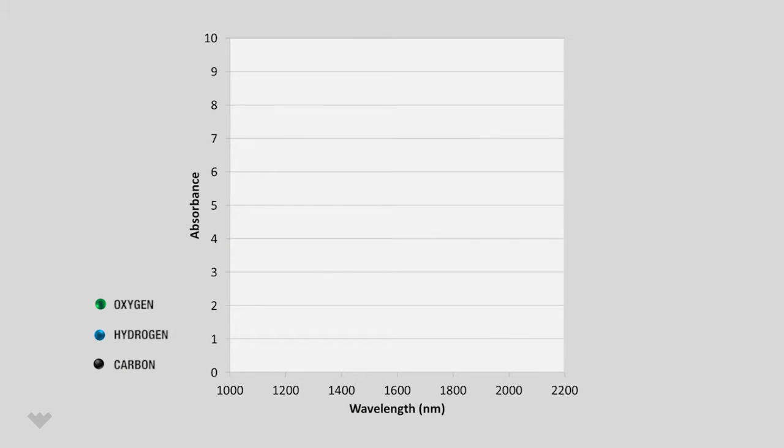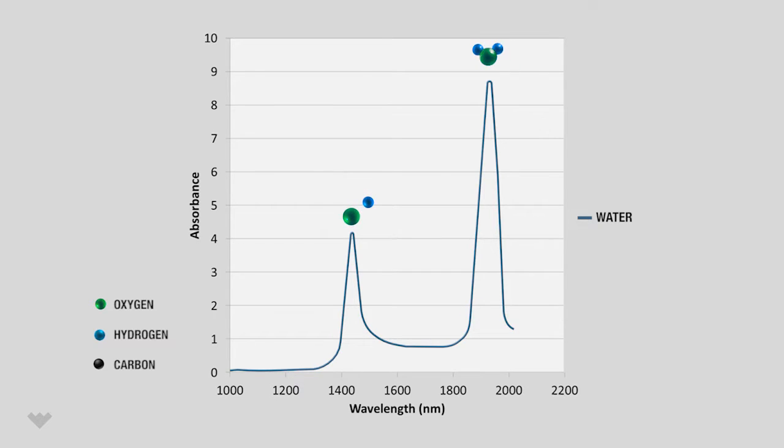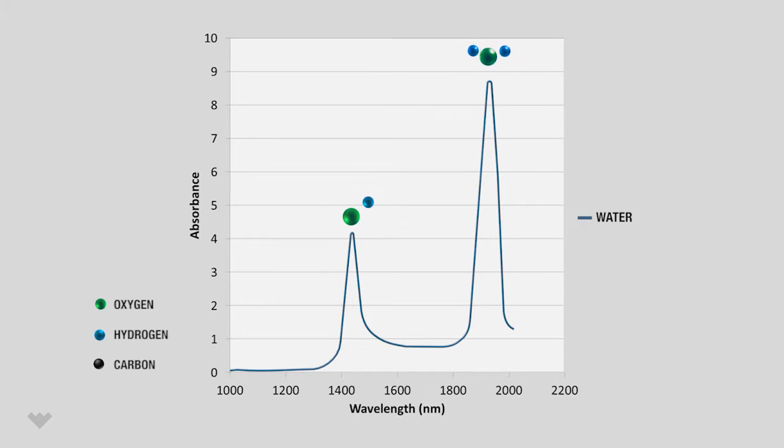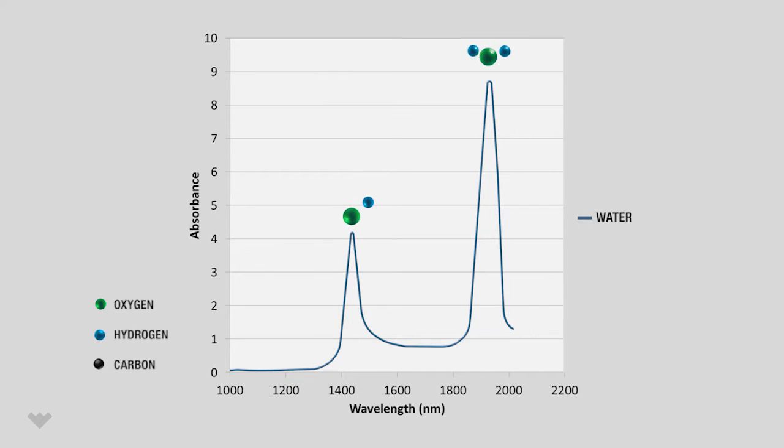Near-infrared spectroscopy is based on molecular vibrations. Water has two strong absorption peaks that are related to the oxygen-hydrogen bond motions. Importantly, these are based on the water molecule itself rather than dissolved components like salt. The strong water peaks enable the meter to provide unparalleled water onset detection capability for any well stream.